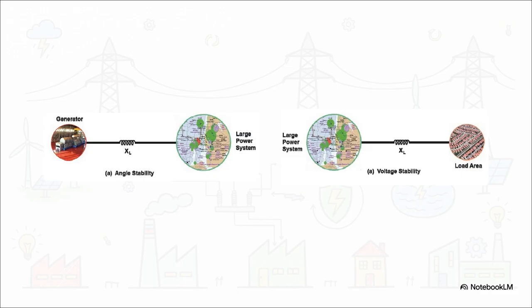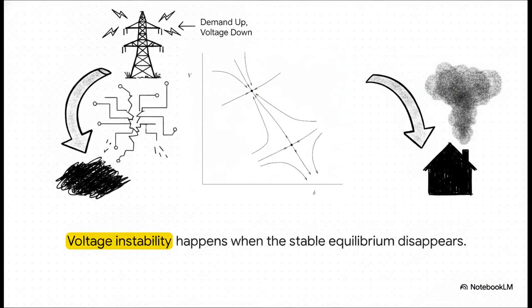The second pillar is voltage stability. This acts as the steady, invisible pressure that pushes power across hundreds of miles of transmission lines to a load area, like a bustling downtown city. Now, if that voltage pressure fails, things go south really quickly. It's essentially a tipping point. As the demand for power goes up and up, the voltage actually declines. And if the system is pushed past its breaking point, the stable operating equilibrium just completely disappears. This triggers a rapid and super dangerous voltage collapse, where the grid basically just gives up on pushing power altogether, plunging the whole area into the dark.